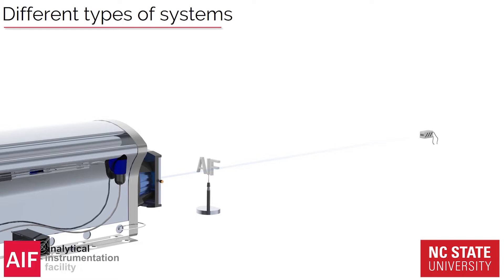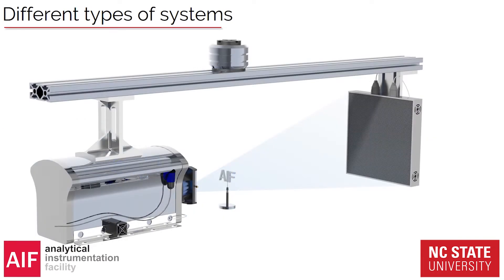You can even use the pencil beam — the first type we ever had, with only one pixel to collect photons. Here you need to translate the sample both up and down and sideways, which takes a very, very long time, and you have very high requirements on stage precision. There are also more novel systems where you have the sample fixed and rotate the rest of the equipment — the source and detector — instead. This is very similar to medicine, where the patient is stationary and equipment rotates around them, though it is typically more unstable. The benefit is that we can increase scanning speed quite a lot.